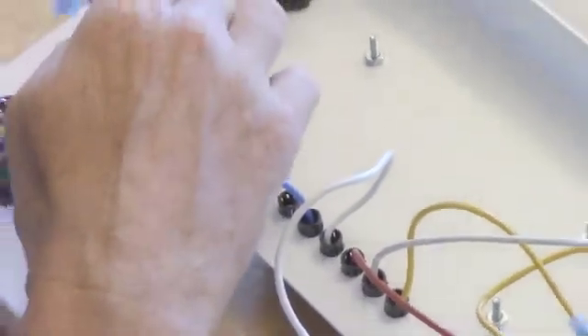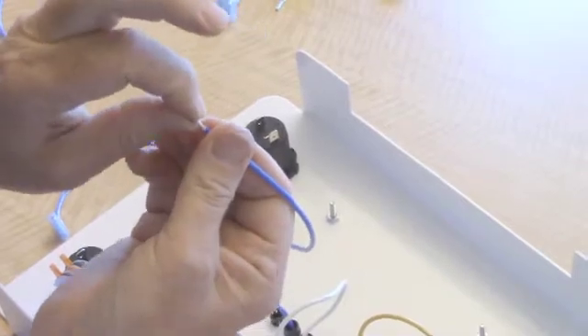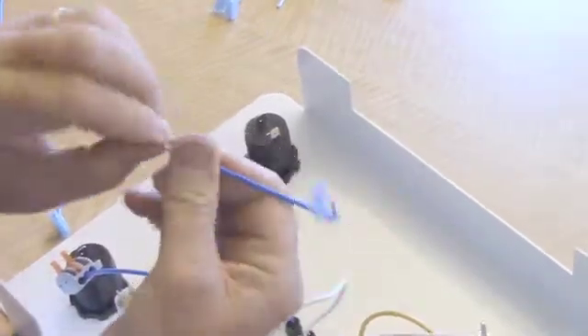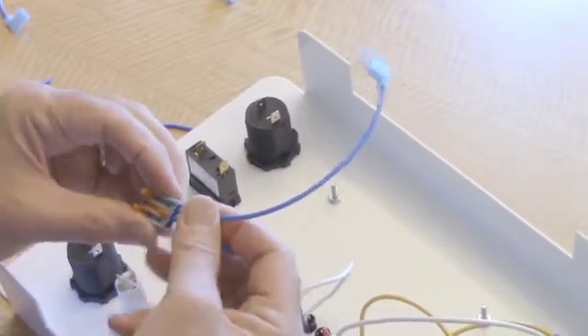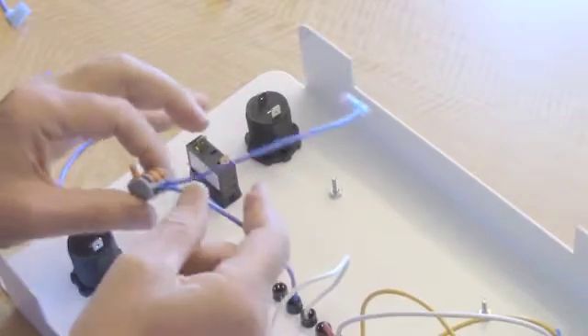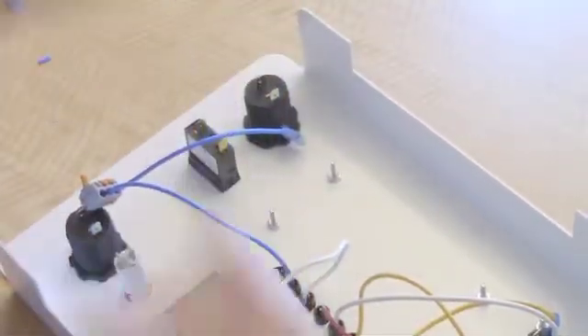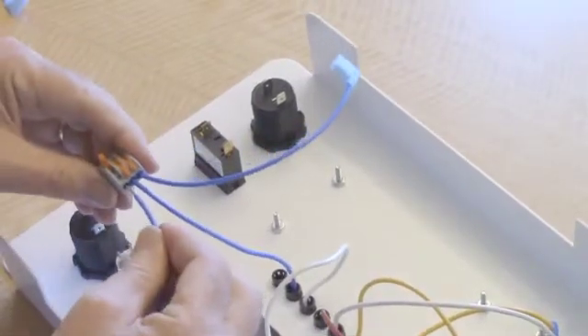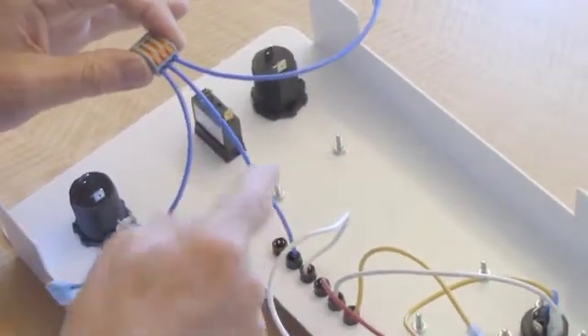Then we're going to use flag connectors to get to both breakers. I'll pull off the insulation on the wire. It's just there to hold the wires together until you're ready to use them. If they were a little bit splayed you could always give them a little twist. Push it into the Wago. Close the lever and give it a little pull to make sure it's good. Take your other wire with a flag on it. Pull off the insulation. Push it into the Wago. Now the electricity will come from the charge controller and into both of these circuits.